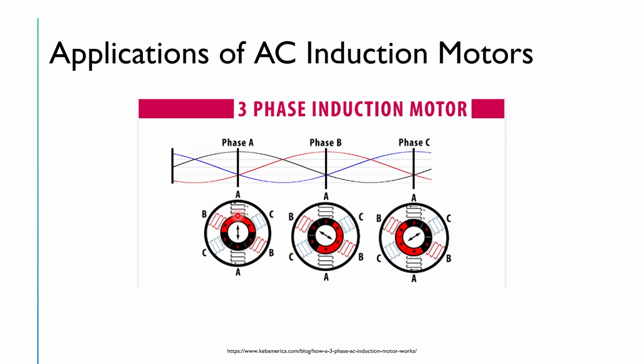Generally, AC runs on 50 Hertz. What this means is that the magnetic field generated by the stator rotates 50 times every second. So not only is this rotating magnetic field leading to a change in flux which induces current into the rotor, but it also rotates in such a way that the rotor follows this magnetic field, in other words, causing rotation and torque.